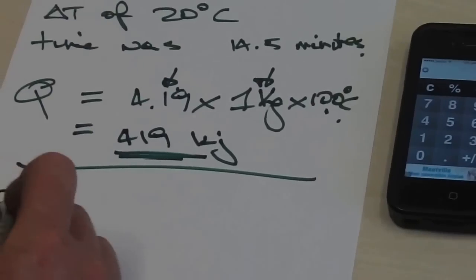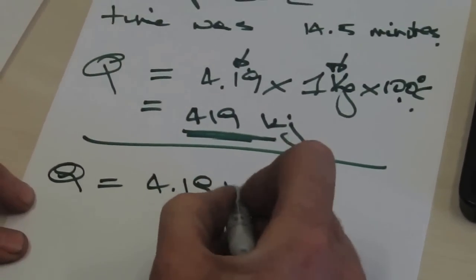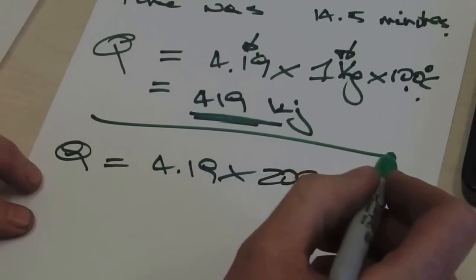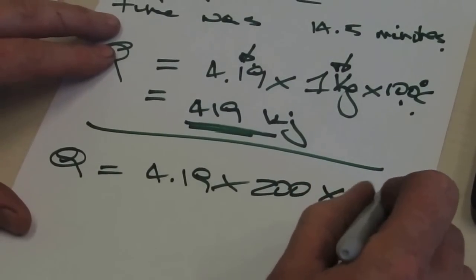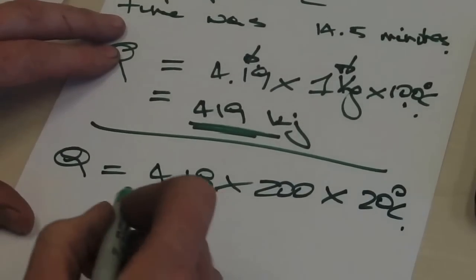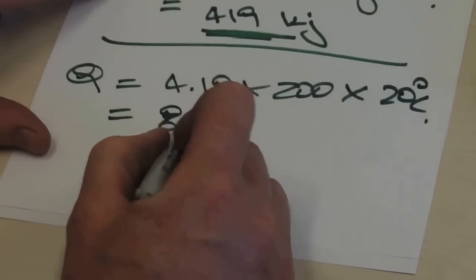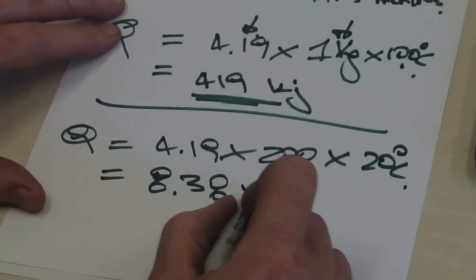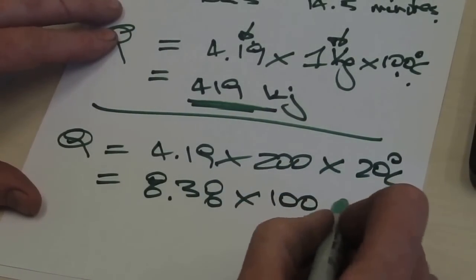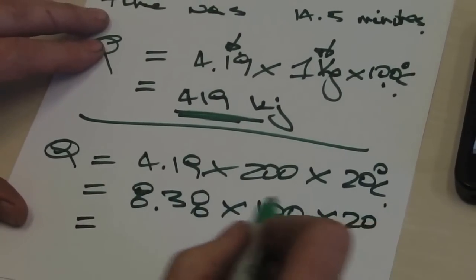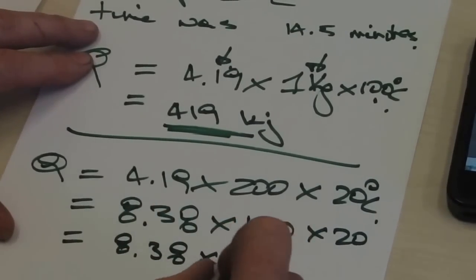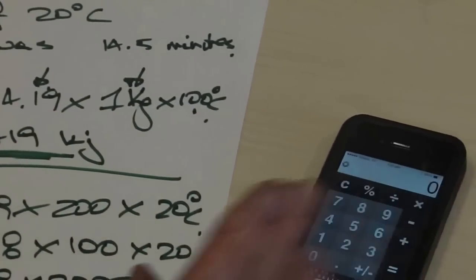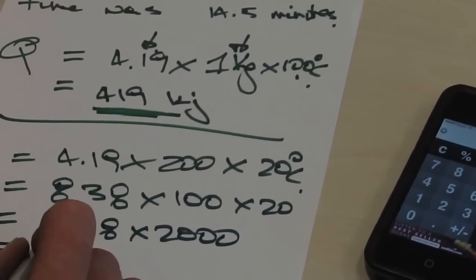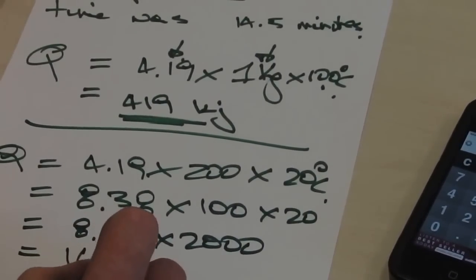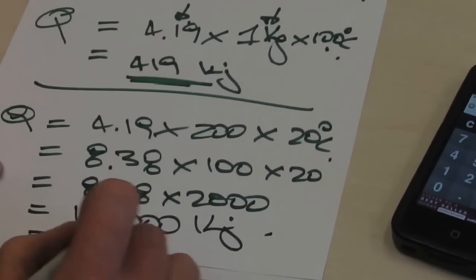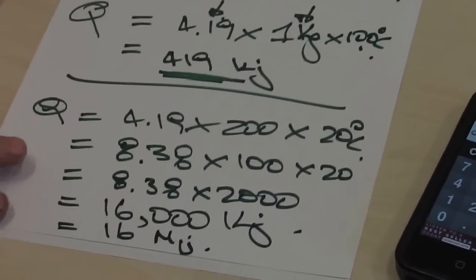So in our case, we were lifting around about 200 kilograms of water, or 200 litres, and we lifted it by 20 degrees C. So let me see, Pete, what have we got here? We've got 4.19 by 200 by 20, which is 4.19 by 4000. So what I'm going to do is just guesstimate that as being around about 16,000 kilojoules, which is equal to 16 megajoules, or equivalent to that.